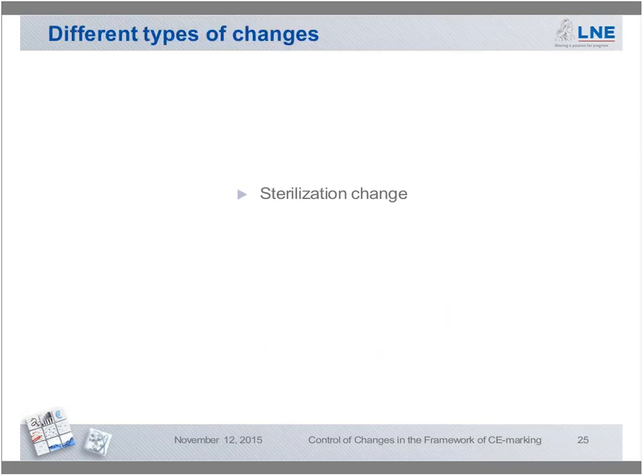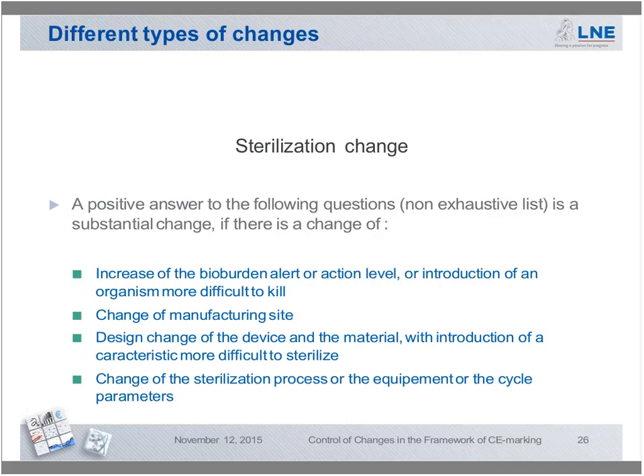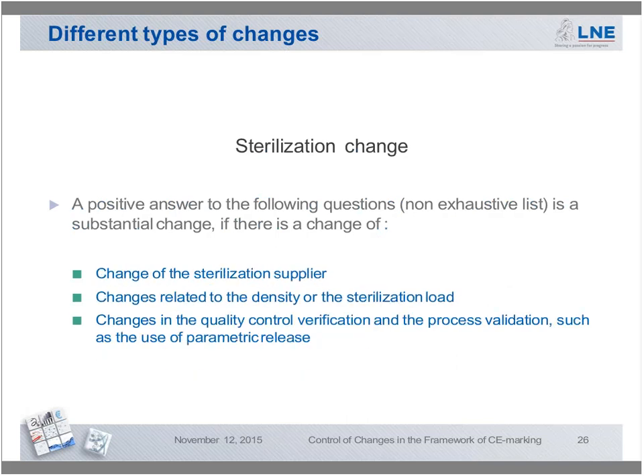For sterilization change, that can be increase of the bioburden alert or action level or introduction of an organism more difficult to kill, change of manufacturing site, design change of a device and the material with introduction of a characteristic more difficult to sterilize, change of the sterilization process or the equipment or the cycle parameters, change of a sterilization supplier, changes related to the density or the sterilization load, changes in the quality control verification and the process validation, such as the use of parametric release.